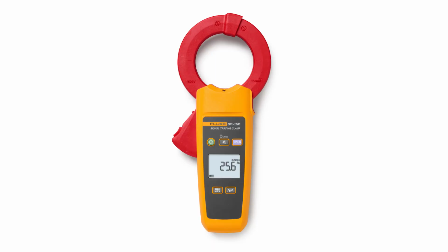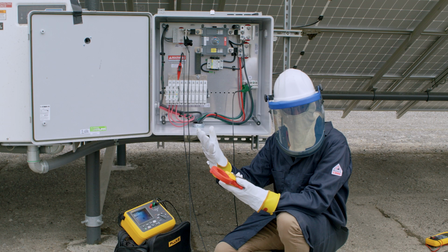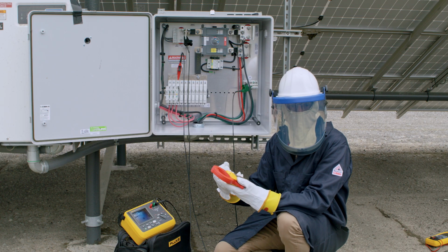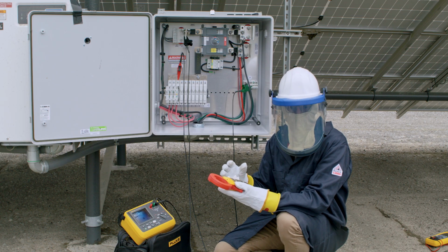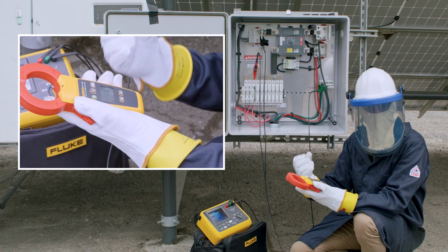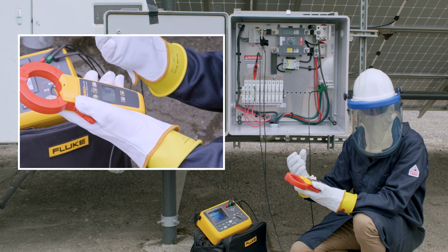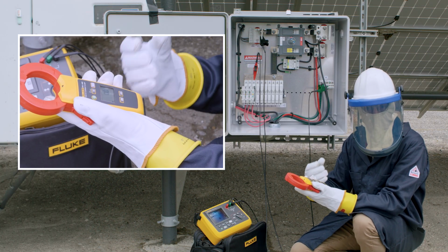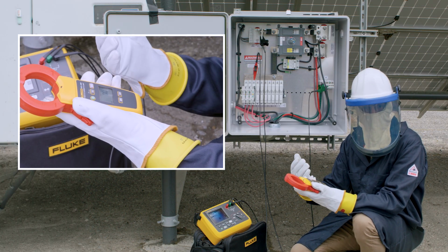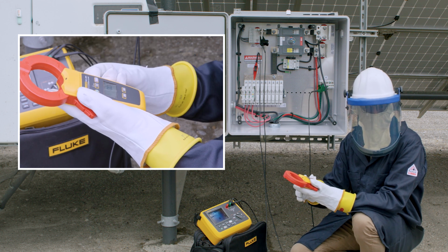In that case, the clamp meter has a feature called band pass. That's the BP button. The signal has two components, a high frequency and a low frequency component. When you turn the band pass on, it's only looking for the low frequency component of the signal, and that is less likely to go to ground through those parasitic capacitance paths.